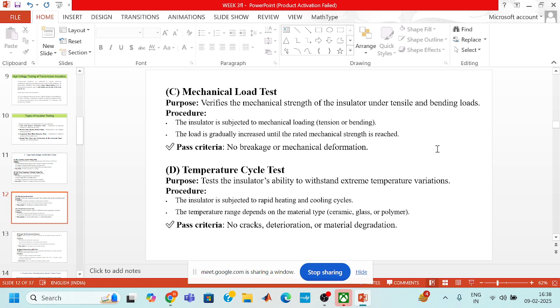Now, fourth is the temperature cycle test. The main purpose of this test is to check the insulator's ability to withstand extreme temperature variations. The insulator is subjected to rapid heating and cooling cycles, and the temperature range depends upon the material which we are using, like ceramic, glass, or polymer. If there are no cracks, deterioration, or material degradation, then the insulator can pass the temperature cycle test.